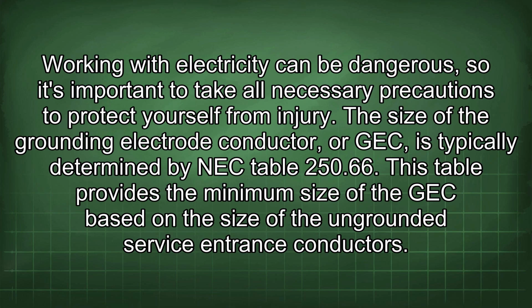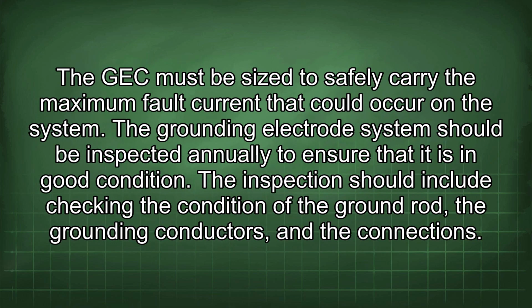The size of the grounding electrode conductor, or GEC, is typically determined by NEC Table 250.66. This table provides the minimum size of the GEC based on the size of the ungrounded service entrance conductors. The GEC must be sized to safely carry the maximum fault current that could occur on the system.